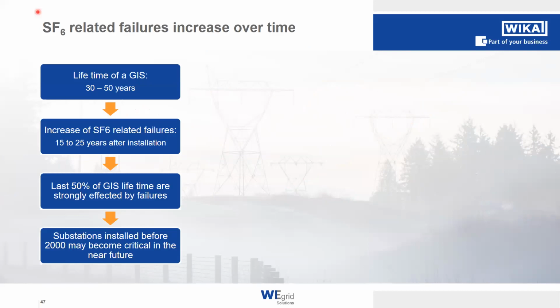So let's take a look at how a GIS is operating in general over its lifetime. From the experience that we have with transmission grid operators and distribution grid operators, generally we can say that the GIS will be in service for 30 to 50 years. What we receive from the market is that SF6 related failures increase at about half of the lifetime of the GIS, so around 15 to 25 years after the installation. That means the last 50% of the GIS lifetime will be most affected by these failures.